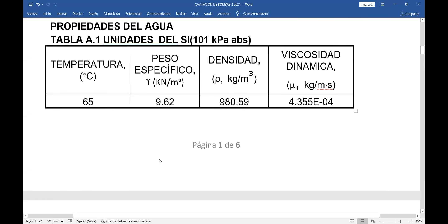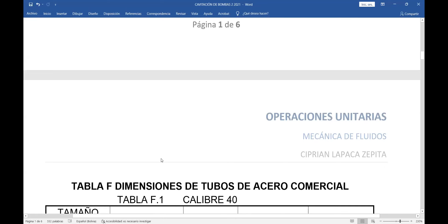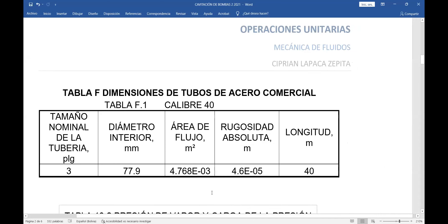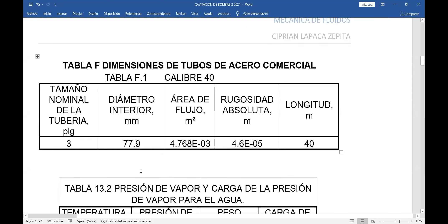Otros datos que requiero son las características de la tubería. Me dicen que es una tubería de 3 pulgadas, acero comercial, calibre 40. De la tabla F de Robert Mott tengo el diámetro interior: 77.9 milímetros. El área es 4.768×10⁻³ metros cuadrados. La rugosidad absoluta es 4.6×10⁻⁵ metros. La longitud total de la tubería es 40 metros.